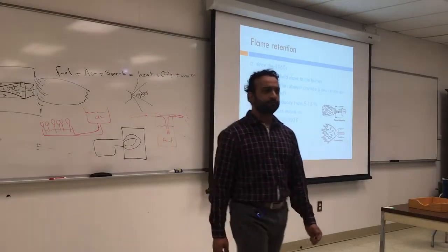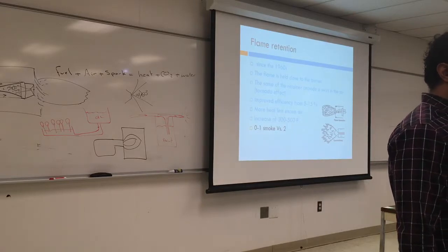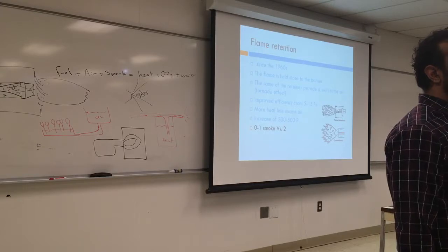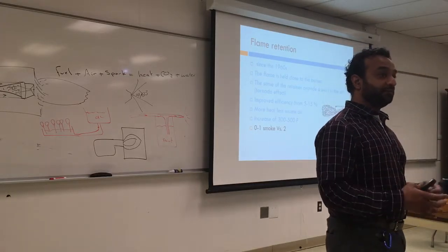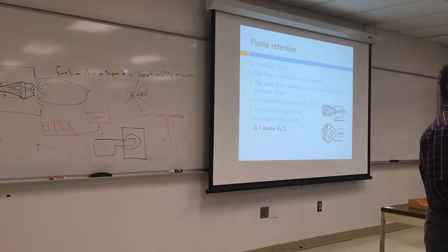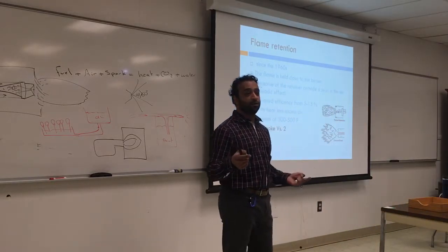Aren't most gas furnaces now more around 97% efficiency? Gas? Yeah. But that's not combustion efficiency. That is thermal efficiency. Thermal efficiency is how much heat you are soaking up from the chamber. Combustion does not go up to that. Maximum is 90. You will never be able to burn the entire fuel. And again, pay attention, gas is different than oil. Oil, it's really hard to get more than 90.